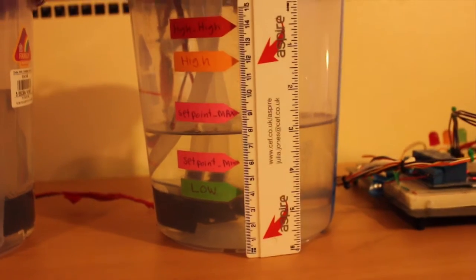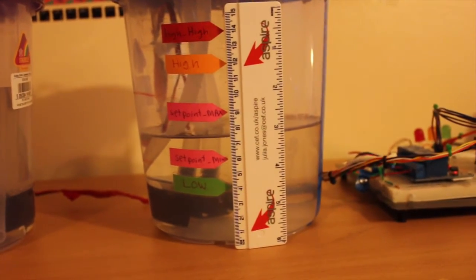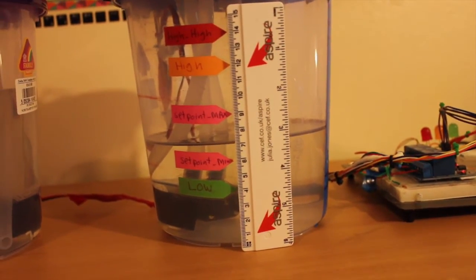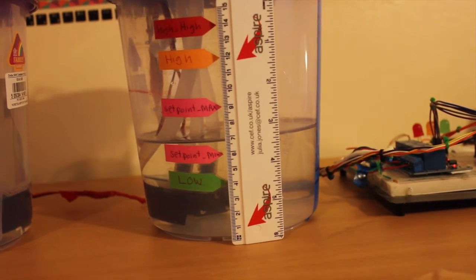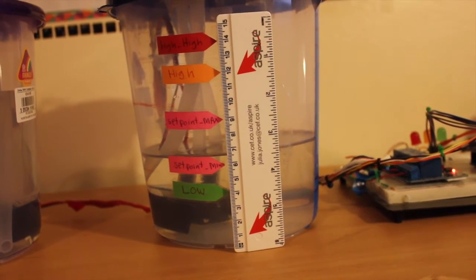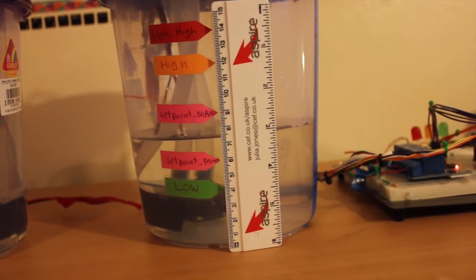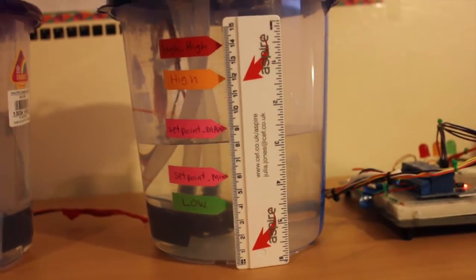We can see here the main tank, that the level is going down. So as soon as we reach the low set point, the outlet pump will shut down and the inlet pump will start. So as we can see here, the level is maintained between these two set points.